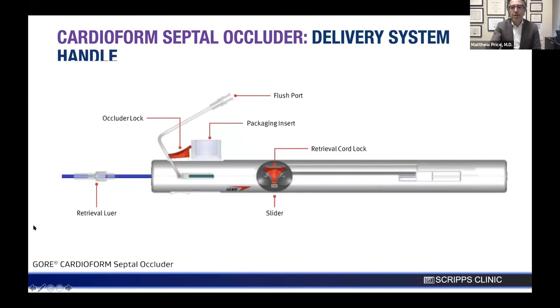There are these two red tabs. Red meaning stop, think before you pull them, okay? This is the locking mechanism. When it's time for us to lock the device after we've deployed it, we're going to slide this red tab back. And finally, after we've locked the device and we like the way it looks, we're going to pull our retrieval cord. This basically pulls off like a beer can tab or a soda can tab. You'll be able to pull that line out, all right? So the key thing is to understand the slider and the lock, and we'll go through that through our case. So that's the device: occluder, delivery sheath, handle.